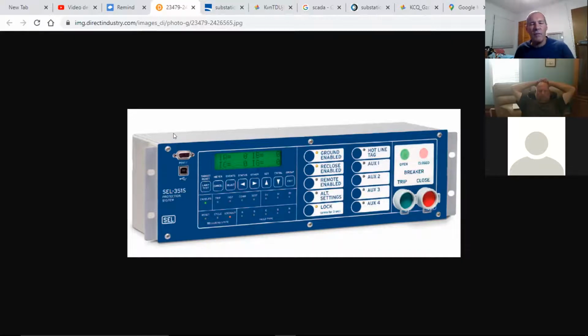So you have information from the RTU, that's the SCADA interface. But it will give you a lot of information and capabilities as far as the pad and the control panel. Obviously, if you want to manually open or close the breaker, what do you do?